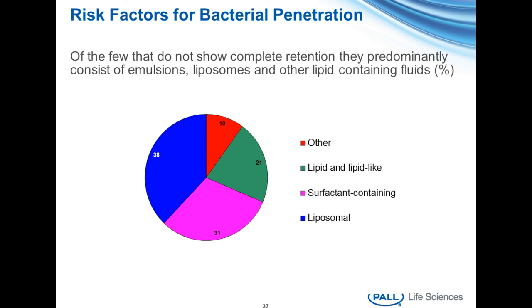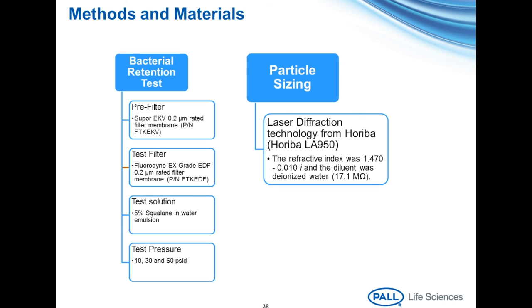In the testing we did here for the early screen, we used SUPOR-EKV as prefiltration followed by a Fluorodyne EX-EDF filter. The bacterial challenge test and the challenge concentration refers to just the EDF challenge. We used the 5% squalane emulsion produced by Microfluidics, as previously described, and tested at three differential pressures: 60, 30, and 10 PSID. Particle size distribution was also evaluated at 30 and 60 PSID.